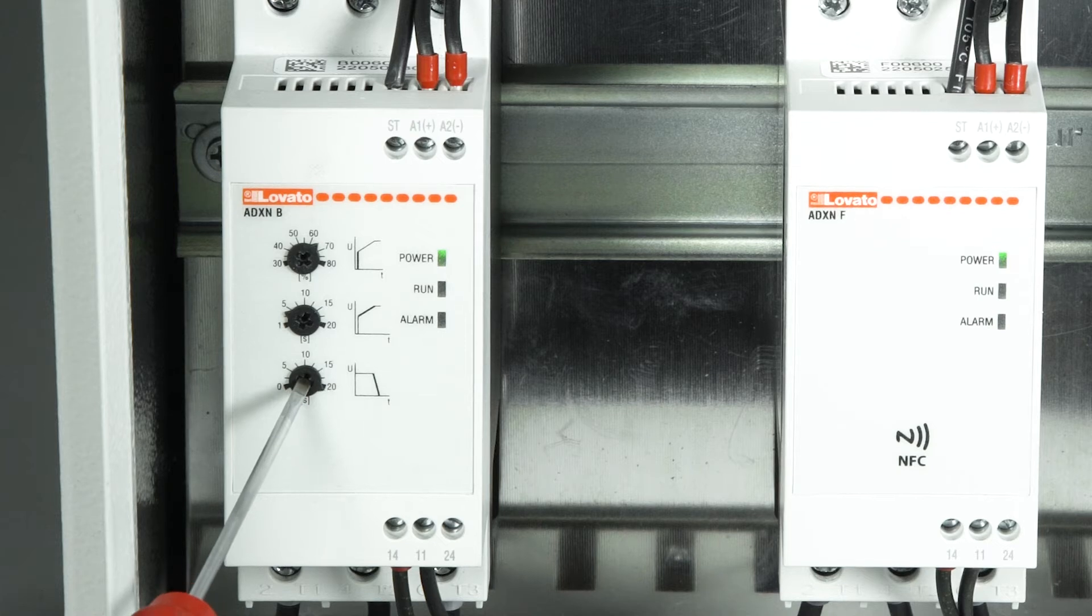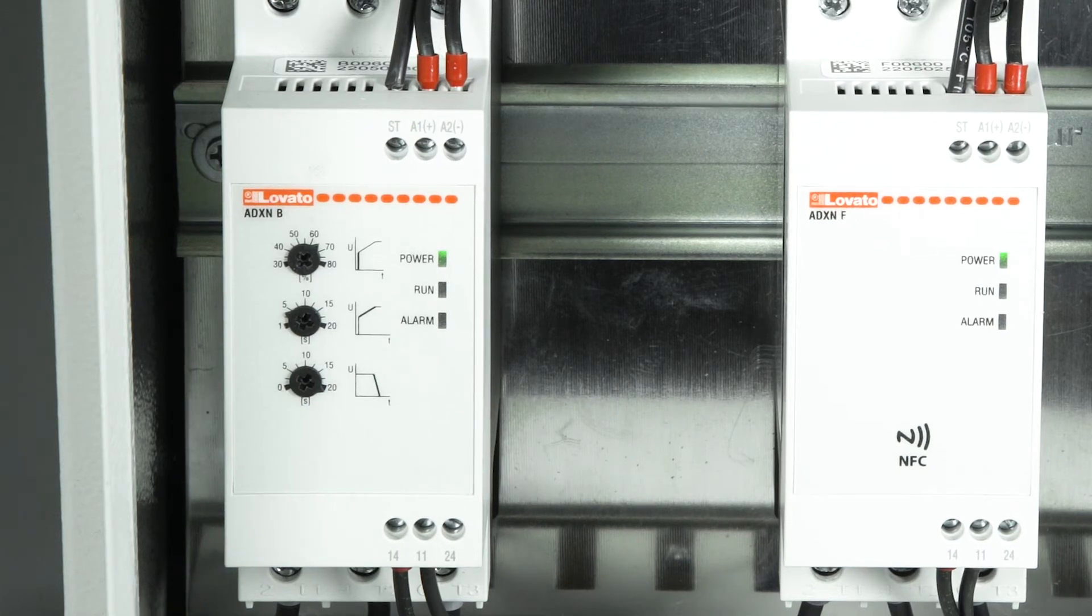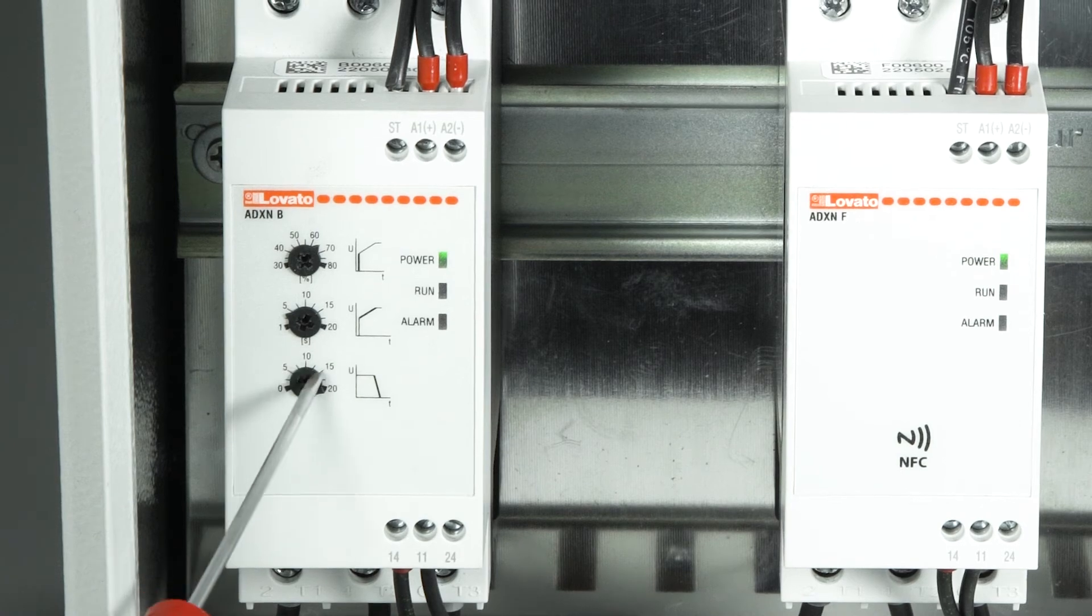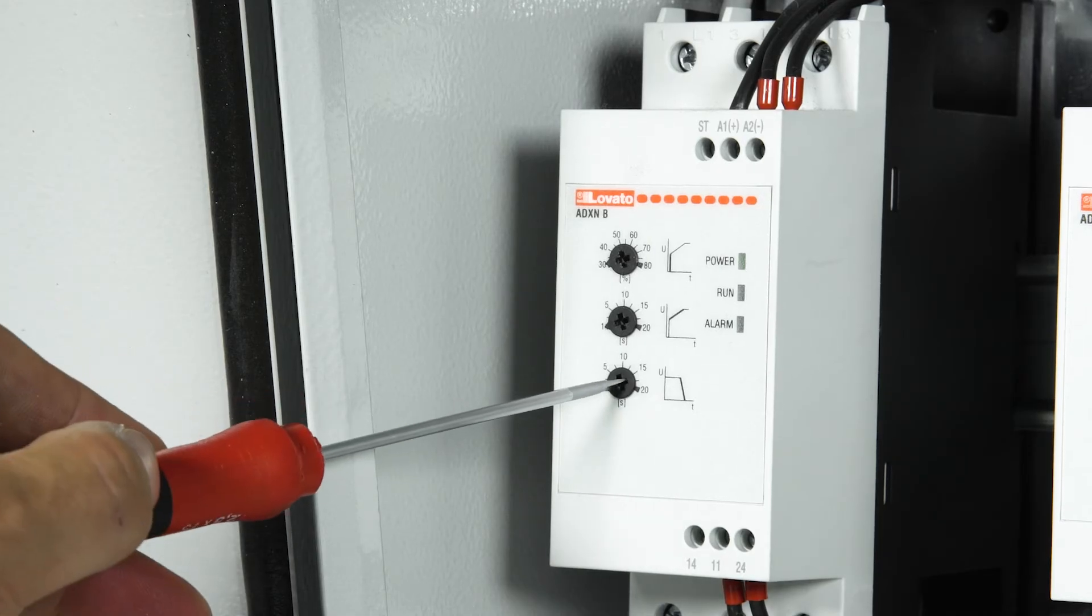The deceleration ramp can be adjusted from 0 to 20 seconds. In case of setting of 0 seconds, the motor stops by inertia with freewheel.